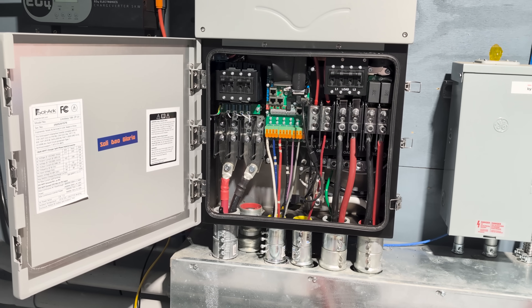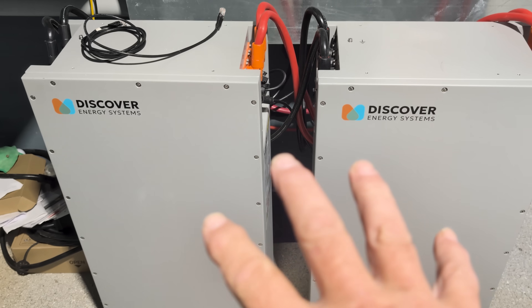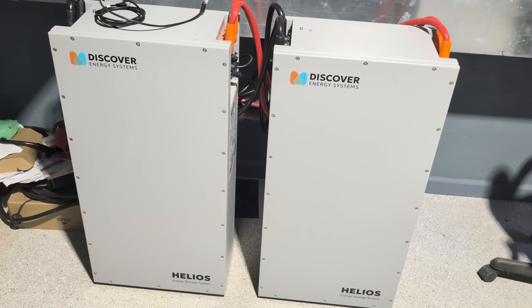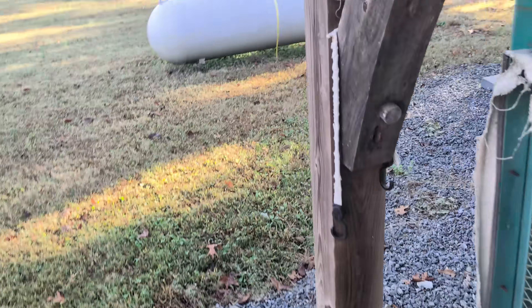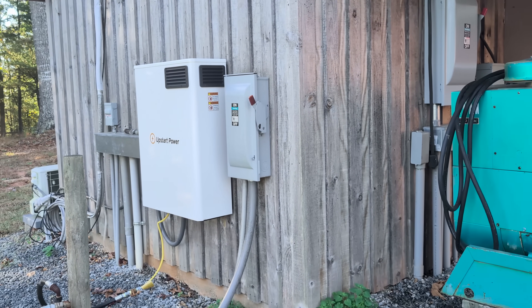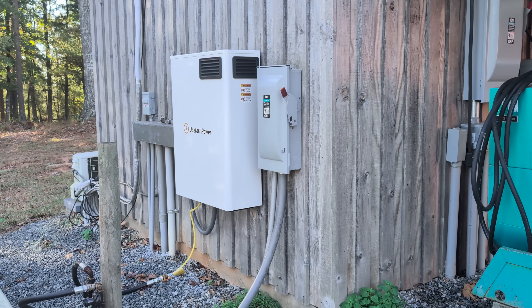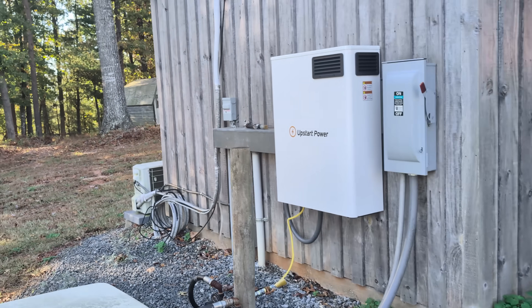The units can be paralleled, so if 1600 watts seems small, over time it's plenty depending on how you size your battery and your system. You can put up to five of the fuel cells in parallel right now. The cost is around $8,000 or more for that unit, but it is providing something that no other generator solution can match at this time — and that's silence and efficiency. I've been working with Upstart on this.